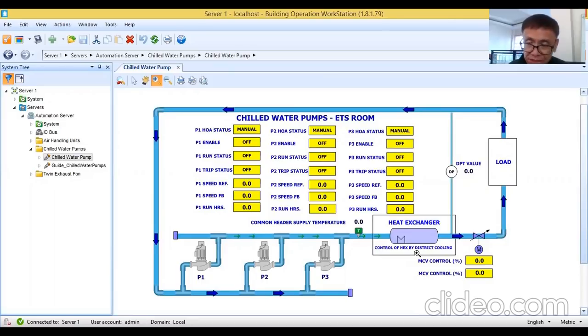Now, basically, these points, BMS points, as I said, if you are the BMS engineer of a solution provider company, first you need to study carefully the project specification. Now you have to look for the mechanical, electrical specification and look for every occurrence of building management system. Now building management system is included in the mechanical specification, okay? Now in the mechanical specification, you will be able to find there the mechanical equipment schedule, okay? Then you will find also there the control schematic diagram.